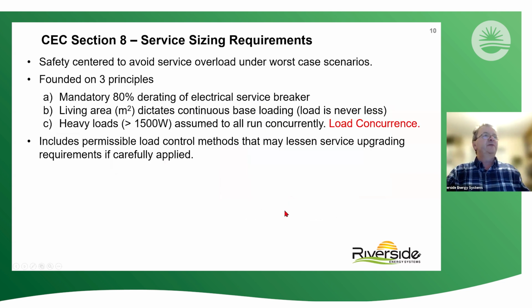When we look at service sizing, Section 8 of the Canadian Electrical Code covers that off. As many of you will know, the Canadian Electrical Code is based on an abundance of caution, and it's very safety centric around avoiding service overloads under worst case scenarios. So sizing is founded on three principles. The first is that there's a mandatory derating of the main electrical service breaker; we're not allowed to let it carry more than 80% of its rating, and this is to avoid nuisance tripping.